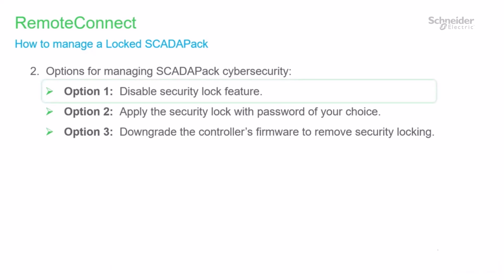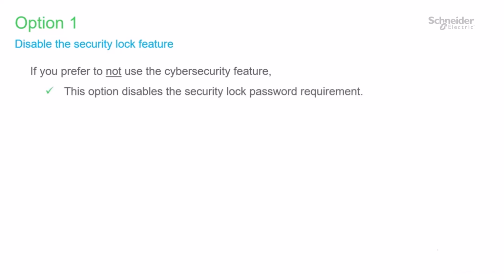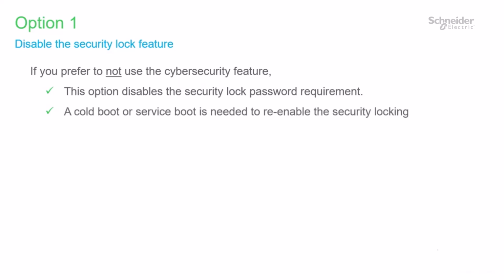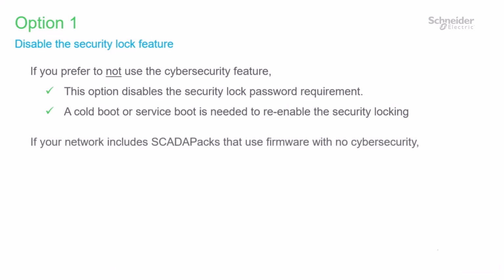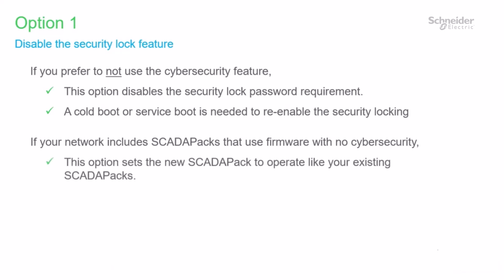We'll begin with option 1, how to disable the security lock. Note that the device must be unlocked or the lock feature disabled in order to edit and write configuration changes to it. This option will disable the requirement for a security lock password. A cold boot or service boot is needed to re-enable the security locking if desired in the future. If you have other SCADAPacks on your network that use firmware without the cybersecurity feature, this option will set the new SCADAPack to operate like your existing SCADAPacks. I'll demonstrate now using RemoteConnect.